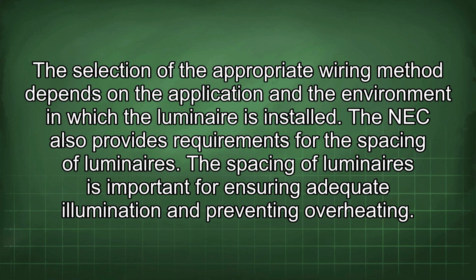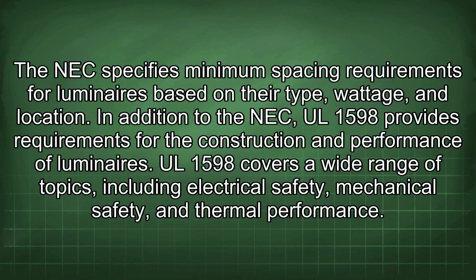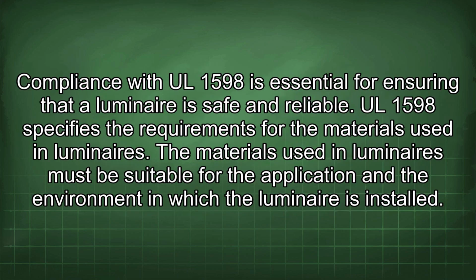The NEC also provides requirements for the spacing of luminaires. The spacing of luminaires is important for ensuring adequate illumination and preventing overheating. The NEC specifies minimum spacing requirements for luminaires based on their type, wattage, and location. In addition to the NEC, UL 1598 provides requirements for the construction and performance of luminaires. UL 1598 covers a wide range of topics, including electrical safety, mechanical safety, and thermal performance. Compliance with UL 1598 is essential for ensuring that a luminaire is safe and reliable.